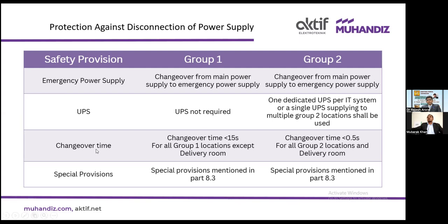Okay. Now coming to the changeover time. A changeover time of less than 15 seconds must be there for all Group 1 locations except the delivery room. In this particular clause for changeover time, the delivery room is also included with Group 2 location areas. It says that changeover time must be less than 0.5 seconds for all Group 2 locations and the delivery room. Okay. For Group 1, it is 15 seconds. For Group 2 locations, it is 0.5 seconds, meaning 500 milliseconds. Okay. Now, special provisions are mentioned in Part 8.3, which can be reviewed in detail.